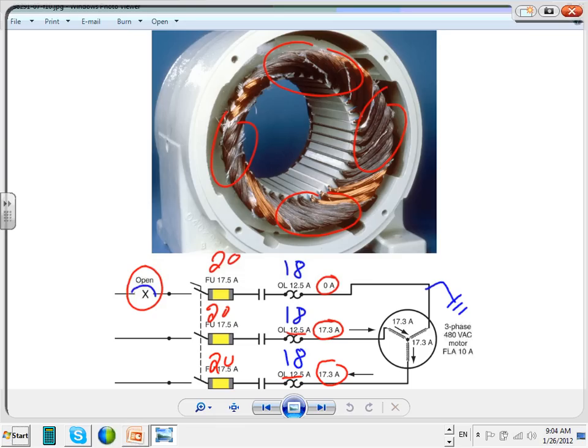Then the fuse says, till the overload stop, don't handle that. That's my territory. I'll protect you. So the fuses, guys, are protection from short circuit and ground faults only, for the most part. If you have a three-phase breaker, if one goes to ground, it pulls all three off. Yes, thank you. If one goes to ground, it will pull the three of them off.